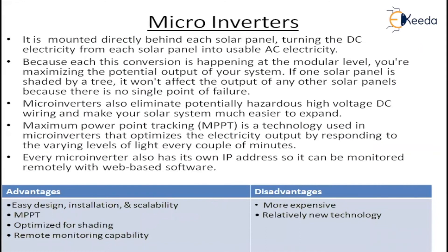Microinverters are mounted directly behind each solar panel, turning the DC electricity from each solar panel into usable AC. From the back of the solar panel junction box we get DC supply — if you put a microinverter, the panel directly gives you AC because each conversion is happening at the modular level. You are maximizing the potential output of your system. If one solar panel is shaded by a tree, it will not affect the output of any other solar panel — there is no single point failure. Microinverters also eliminate potentially hazardous high-voltage DC wiring, making the solar system much easier to expand. There is no requirement for high DC wiring systems.